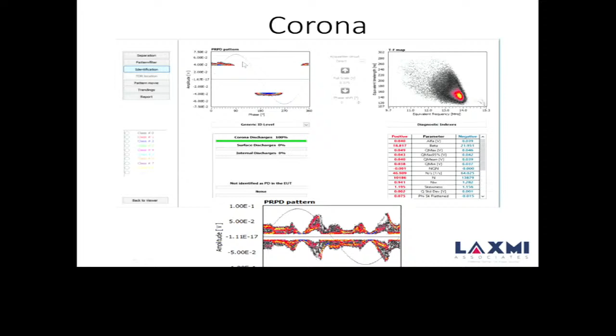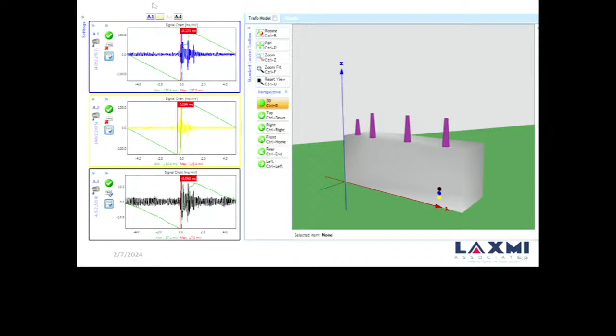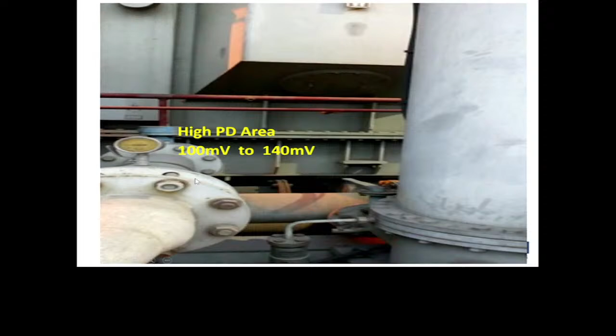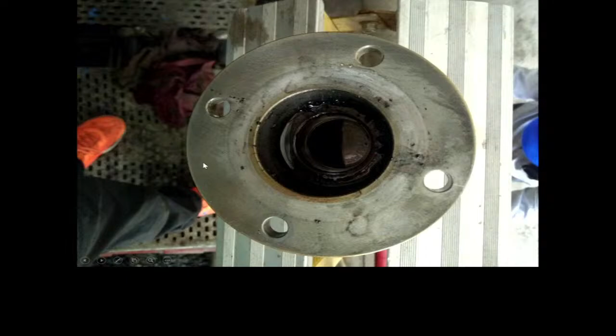Acoustic PD is covered per IEEE C57.127. I'm skipping all that because time is not there. These kinds of acoustic and vibration waves are generated, and they have a different nature when in steel, in oil, or in a deflection in surface area; each has a different pattern.